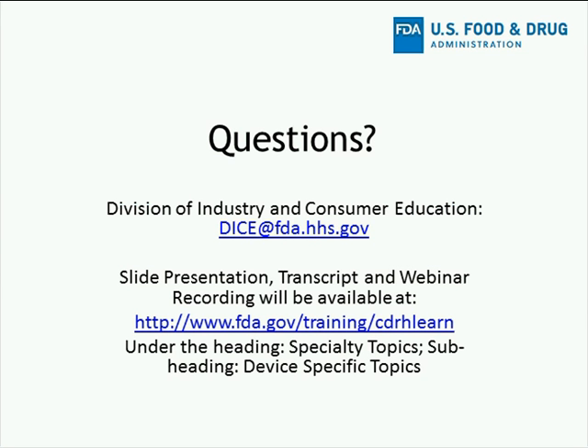But, as you know, for a special 510(k), if you're modifying a cleared product, you would do a risk analysis to identify the types of verification and validation activities that are necessary for that change. So, like I said, when you're doing a study that's addressed by the guidance as part of your V&V activities, we do recommend you follow the guidance. Certainly there are other activities that are V&V activities that may not be addressed by the guidance also. And we're also happy to help with any questions on particular situations that you have that might be unusual as well. Okay, great. I have one other question as well, if that's okay.